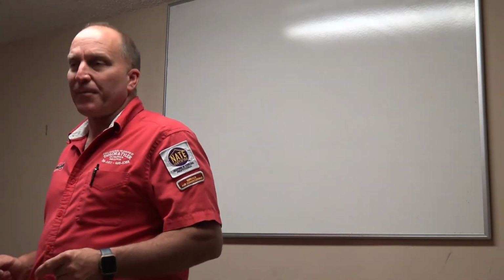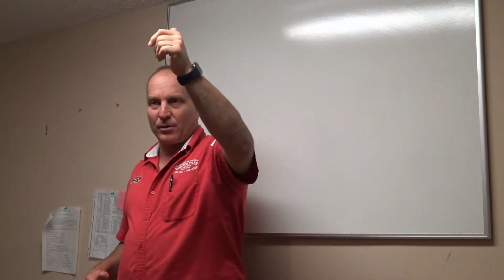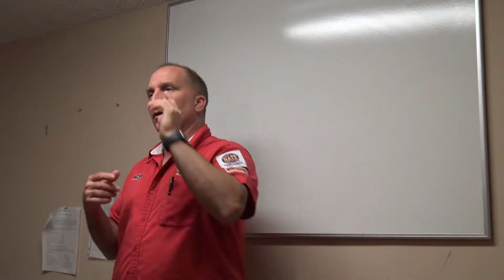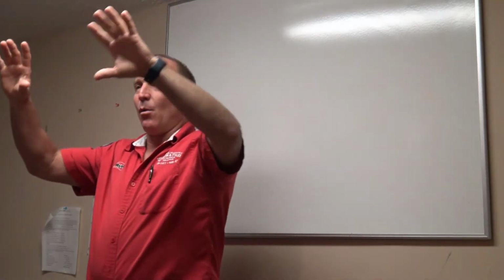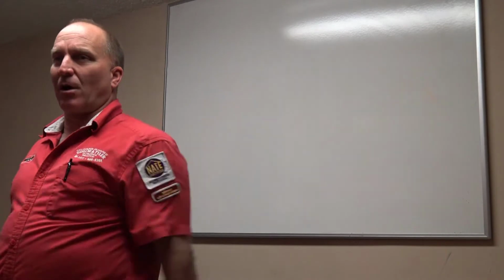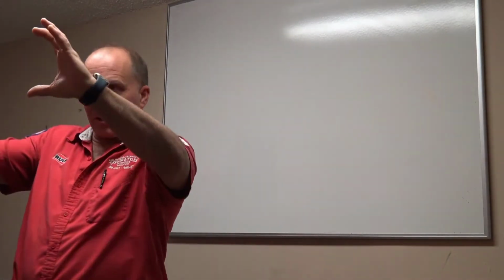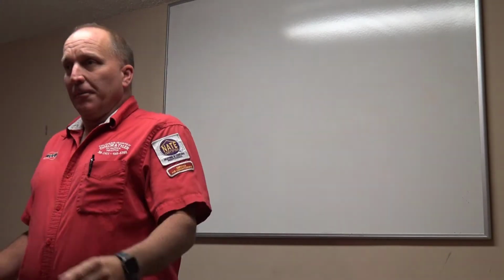Trust me, everything that you do, you want to take a picture, okay? You want to take a picture of the condenser, upload a picture of the condenser. Take a picture from here to the end of the wall, 10, 12 feet away, of the installation. I want to be able to see how that system is installed from a distance, so I can see the furnace, the coil, the plenum, and just kind of get me the whole picture of it.